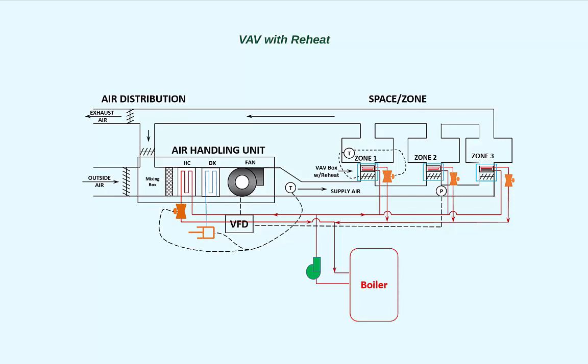DX units have minimum face velocity requirements. If the velocity falls below this specification, moisture that condenses on the evaporator won't trickle down into the condensate pan as quickly. Additionally, less airflow means less heat to be removed from the airstream, and the evaporator's temperature may drop too low. These two issues are a recipe for ice to form on the evaporator. So if you install a split system or heat pump on a VAV design, you need to make sure the design minimum airflow never creates a situation where you fall below the minimum face velocity required at the evaporator.